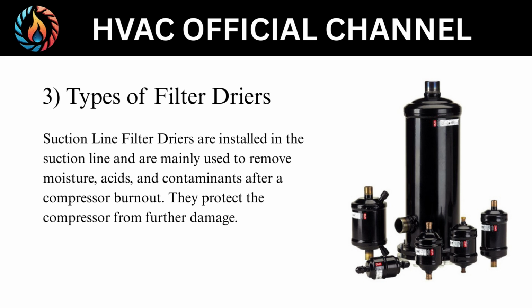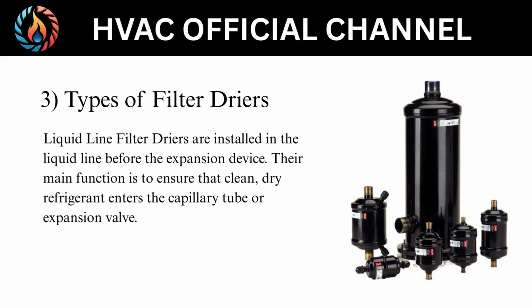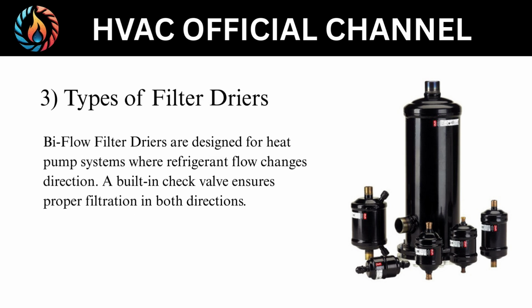Suction line filter dryers are installed in the suction line and are mainly used to remove moisture, acids, and contaminants after a compressor burnout. They protect the compressor from further damage. Liquid line filter dryers are installed in the liquid line before the expansion device. Their main function is to ensure that clean, dry refrigerant enters the capillary tube or expansion valve. Biflow filter dryers are designed for heat pump systems where refrigerant flow changes direction. A built-in check valve ensures proper filtration in both directions.